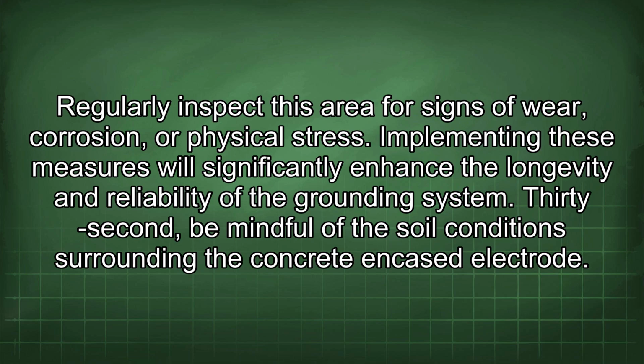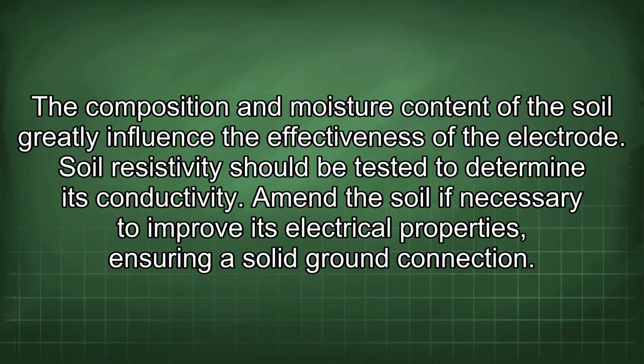32nd, be mindful of the soil conditions surrounding the concrete encased electrode. The composition and moisture content of the soil greatly influence the effectiveness of the electrode. Soil resistivity should be tested to determine its conductivity. Amend the soil if necessary to improve its electrical properties, ensuring a solid ground connection.